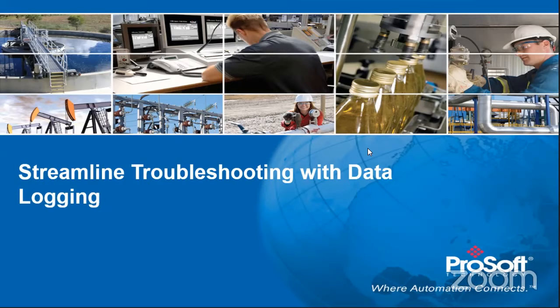So you said there was like 1,440 hours of data measurement. Is that basically the accumulator, the previous day value, the day value? That's per hour. Every hour the module automatically cuts an archive record, which consists of everything from the flow weighted average of the process inputs to temperature and pressure correction factors to all your measurement data. By default, we set up our archive structure for API 21.1 or 21.2 compliance, which I think calls for about 36 values for the measurement.